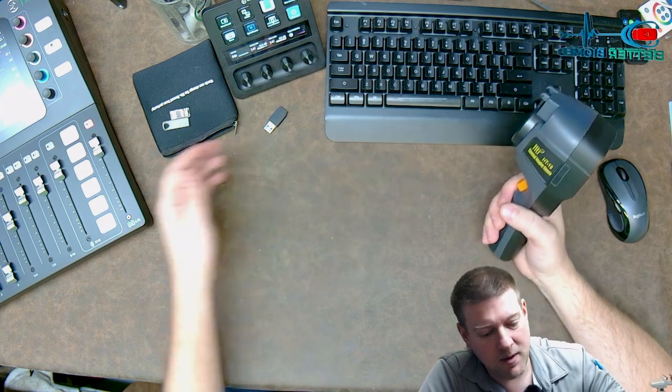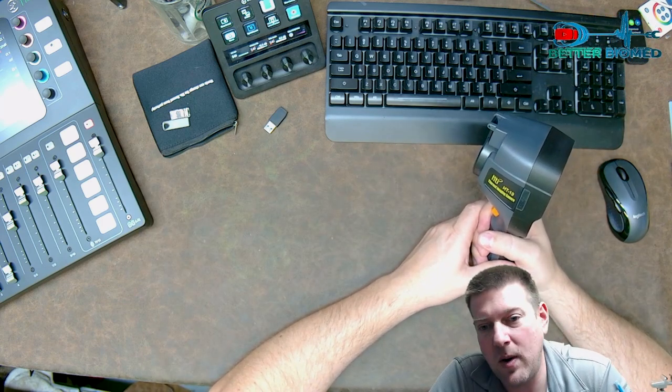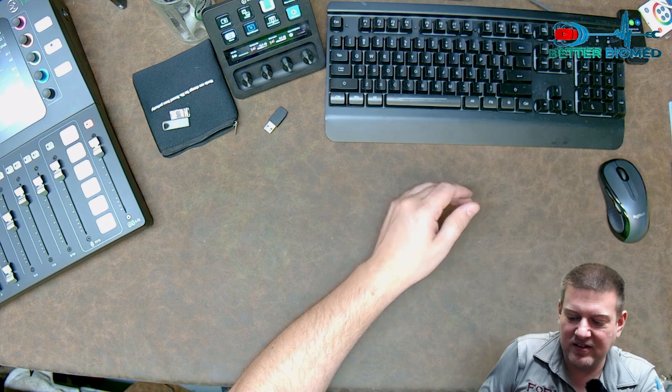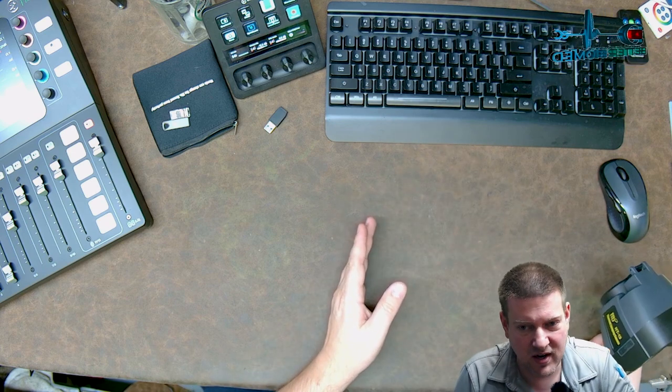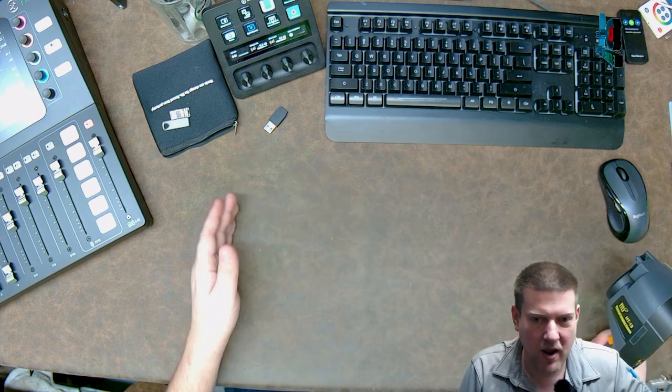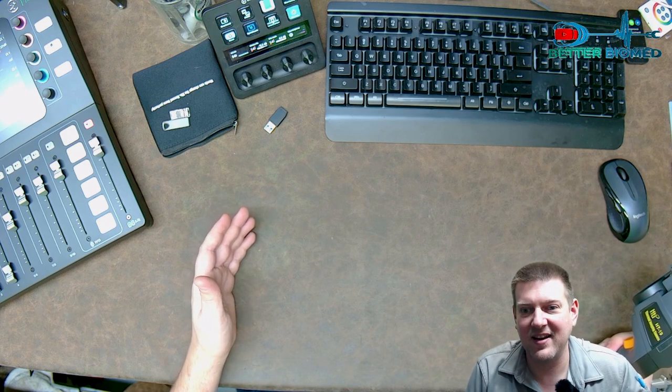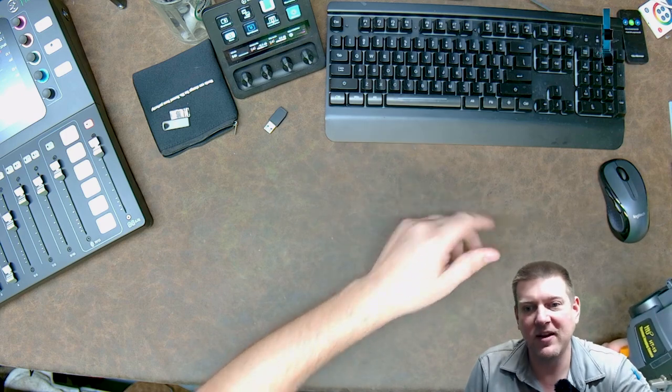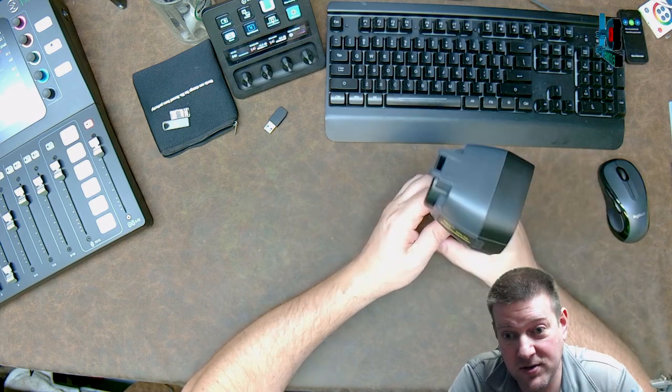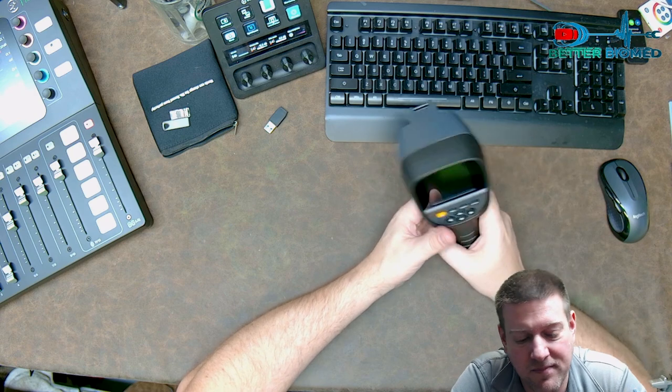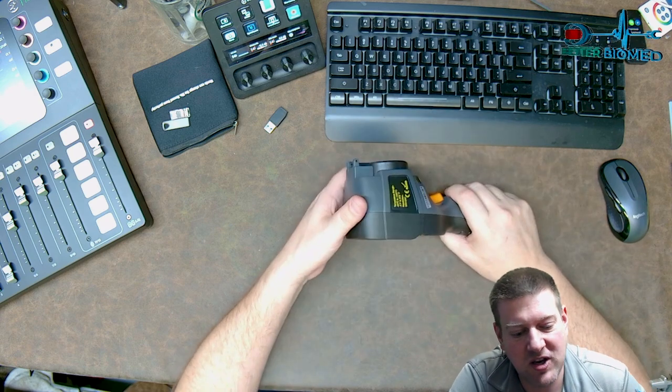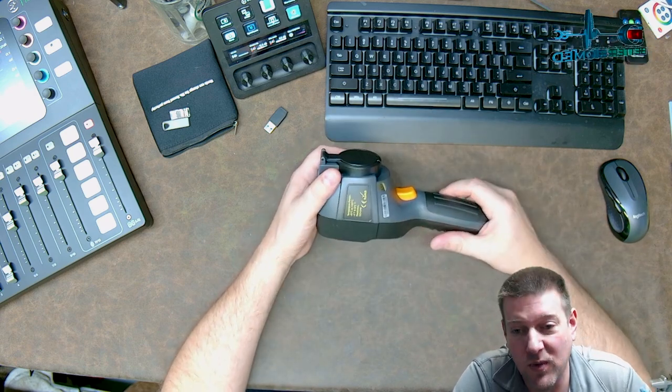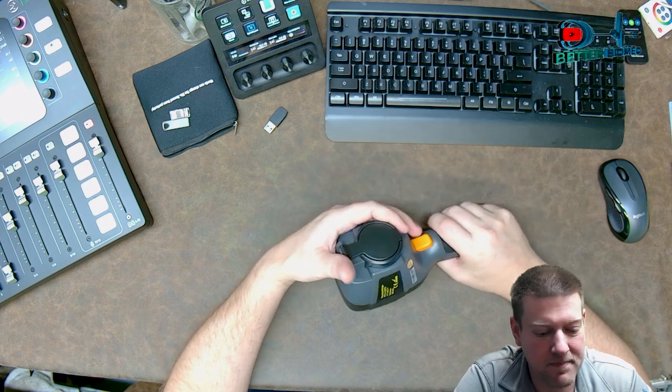Now, there's other things you can do. You can check relays and stuff like that with one of these because anything that transmits current is going to get warm. And as it gets warm, you can test it with one of these. And you can also see circuits that are de-energized because they won't be getting warm. And it's almost impossible to find out where that is on a circuit board without one of these cameras, without using your probes and your multimeter and oscilloscope or something like that. With one of these cameras, if I were to put a power supply here and power it up and it has no output, I can actually scan this and I can tell you that these components over here are getting warm. These ones here are warm, but hey, the output side is cold. It's cold, cold. Like it's not getting any warmer. So immediately go back to your rectifying diodes or something and instantly check it out.